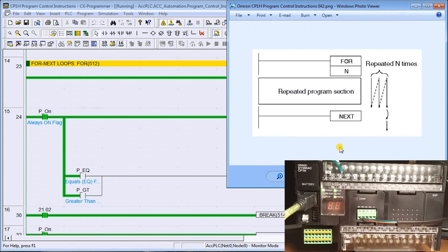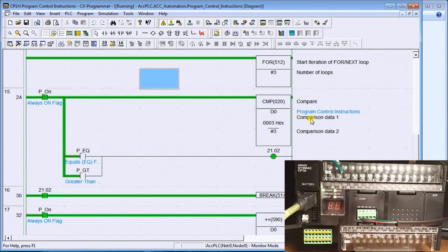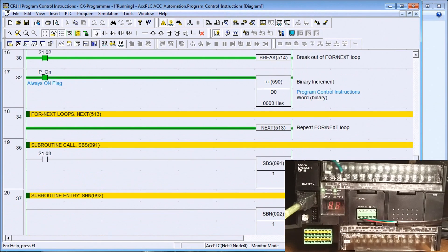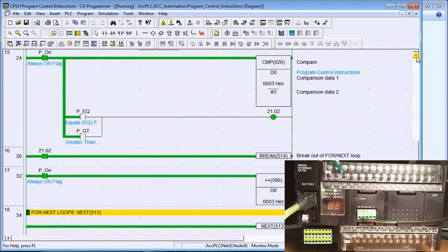To get out of a for-next loop you either finish the loop or you use a break. The break will get you out of the loop before you finish the number of repeats. In this example I have the for-next loop set to three loops. Then we do a compare — we compare data memory zero to the number three, and if it's equal or greater it sets a bit on. When that bit turns on it causes the break. If not, we add one and then the next sends us back to the beginning to do the loop again.